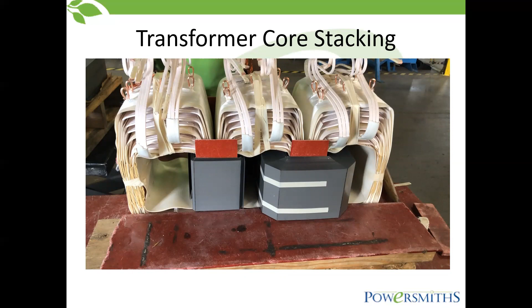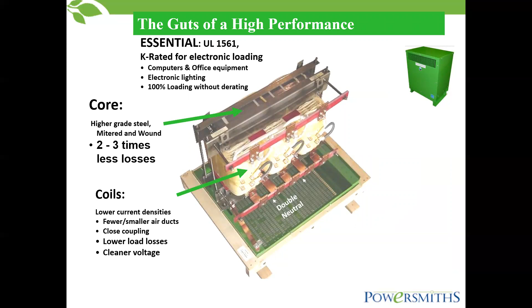This is just an example of our stacking of our cores. And the coils - smaller air ducts, close coupling, cleaner voltage. Now you're getting a cleaner output voltage of what's coming into that particular transformer. And again, the coil height, I already mentioned it, it's a better transformer design.